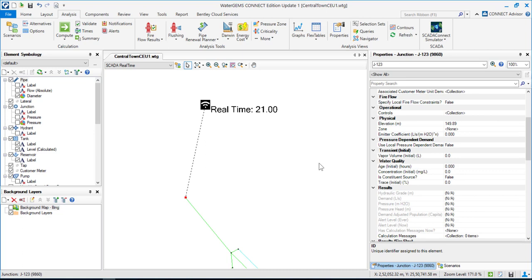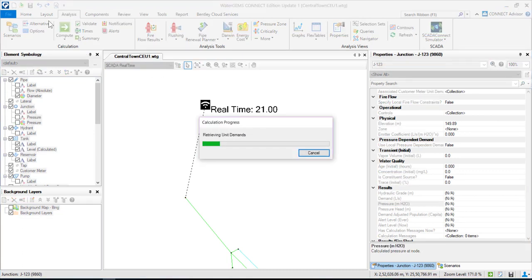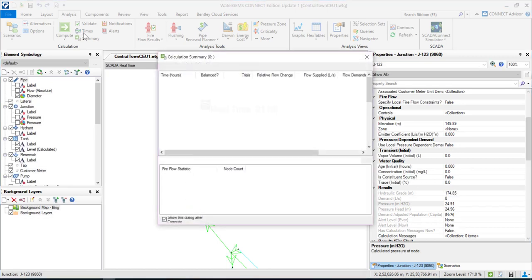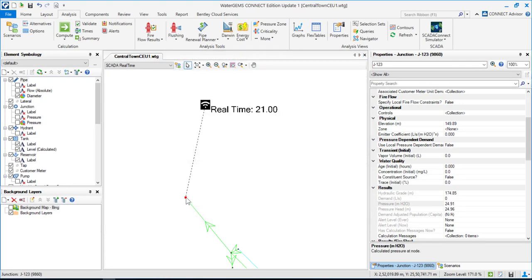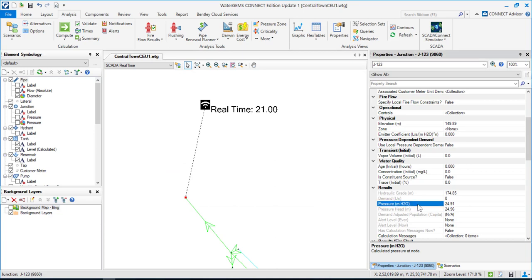Let me hit Compute. This is the hydraulic model value of that junction for pressure: 24.91 meters. However, the real-time value is 21 meters. So you can see there is some difference — the model is indicating 24–25 meters of H₂O pressure, whereas the real-time value from the SCADA sensor is around 21 meters.